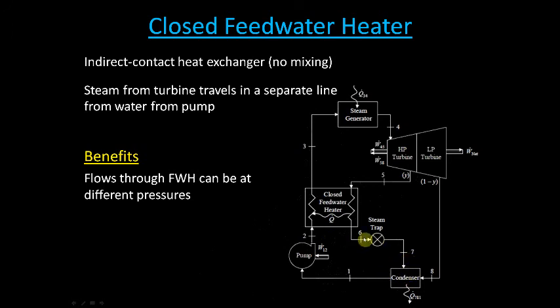However, we do have this issue where the flow coming out of the closed feed water heater is going to have to go into the condenser. And you're going to have the same issue with the condenser in that you need these to be at the same pressure before it goes to the pump, or else we get backflow. So we have this thing called a steam trap, which we'll explain further in a different video. And the steam trap is going to allow us to lower that pressure. So the cost is that we have to add this steam trap to lower the pressure before it mixes in the condenser.